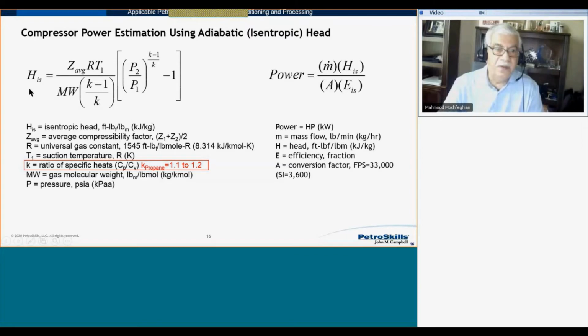In thermodynamics, it means constant entropy process. In real world, meaning 100% efficient. Do we have 100% efficient? Not really, only in our dream. But we utilize this ideal process to determine the head, and then we will multiply head by mass flow rate, divide by efficiency of process, and divide by conversion factor, we get the actual power requirement for our compressor. Of course, I'm talking about thermodynamic power. If you want mechanical power, then we have to apply the mechanical efficiency as well to determine the power of the driver.